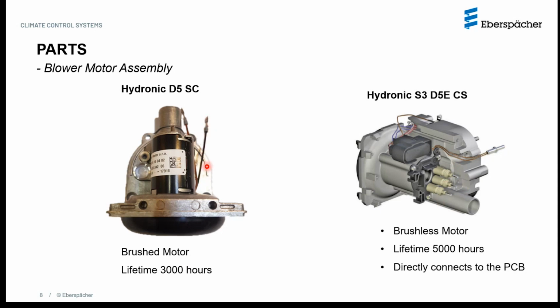When you have too many connections, of course, the chances of failure always will increase because of a loose contact or a badly crimped terminal, etc. All of that is avoided by using a direct contact to the PCB board. Having said that, this unit also has a much higher protection rating against dust and dirt and debris, but that's only the case if the seal is maintained. So at any point in time, if the heater is being torn apart for service repairs, then it is expected that the cover on the motor is always replaced, because that's the part that forms a perfect seal between the motor assembly and the ECU. So that seal will be compromised once you separate it apart. So every time you pull it apart and then reassemble it, you have to put in a new cover.